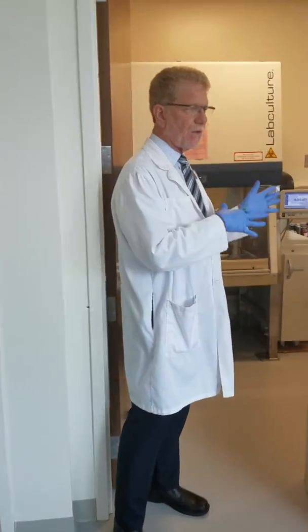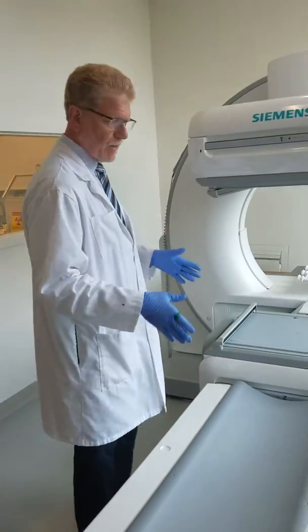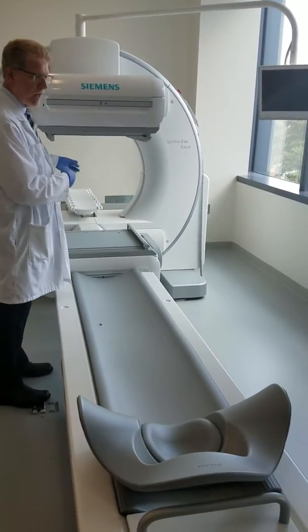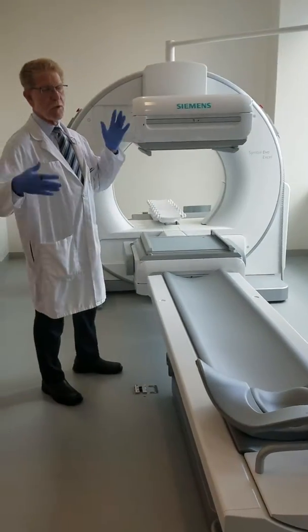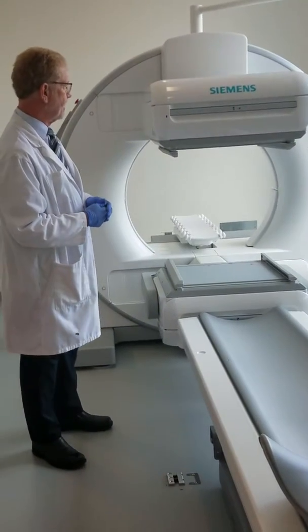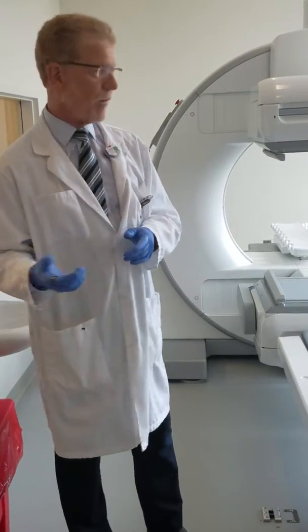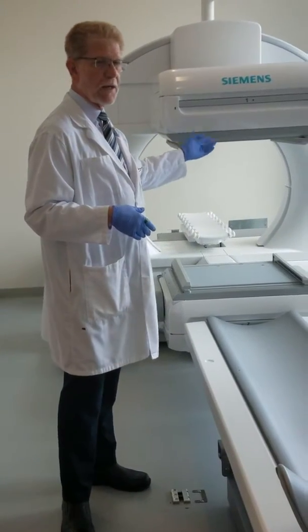After you're done in the hot lab with preparation of the radiopharmaceutical, QC of everything, and QC of the scanning camera, you inject the patient with the radioactive isotope, bring them in here, and set the patient down on the table. You might do a whole body bone scan — this table goes all the way in and comes back out, giving you a whole skeletal scan, both anterior and posterior, because you have two detector heads. This also spins around in a circle so you can get a SPECT scan — single photon emission computerized tomography. Or if you just wanted single spot views, you could do an anterior and posterior or just an anterior.